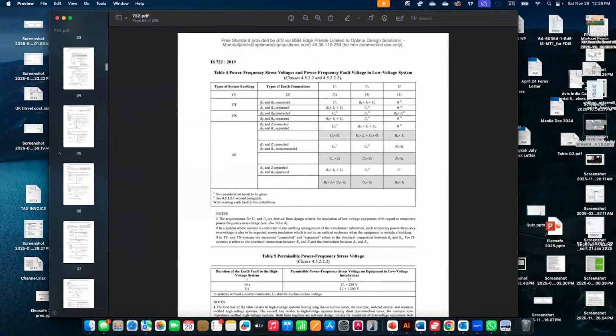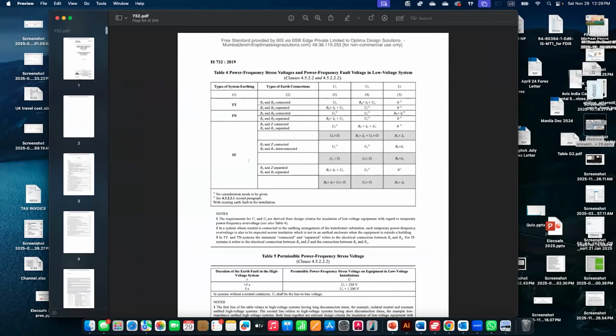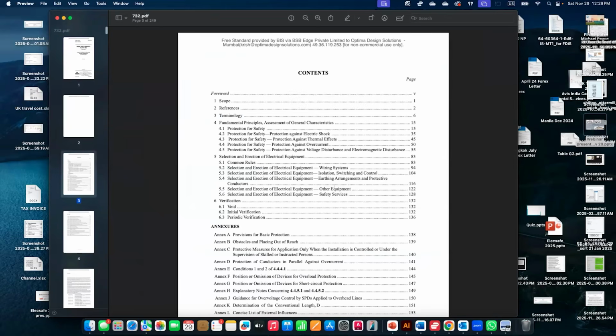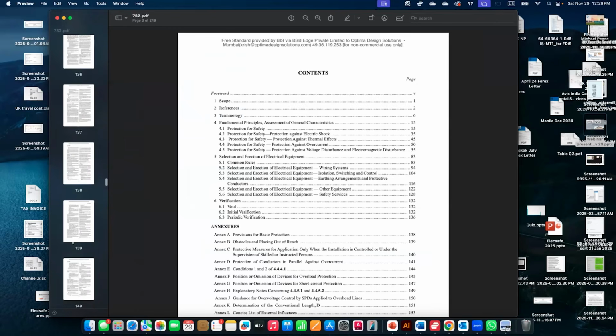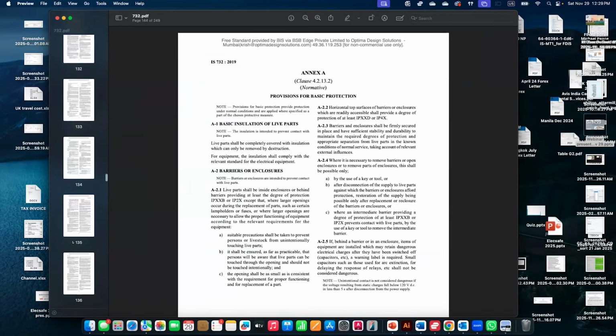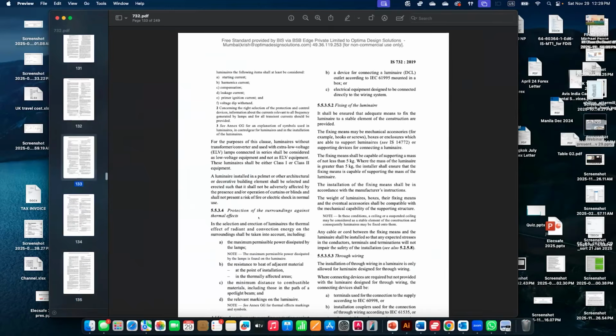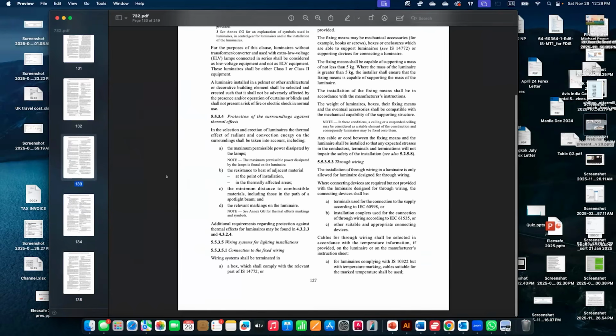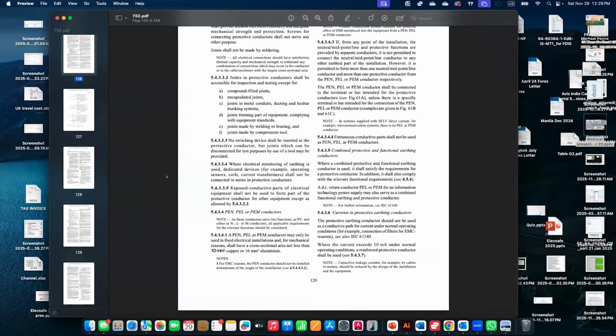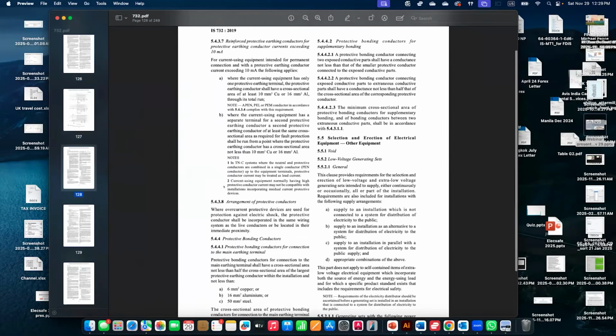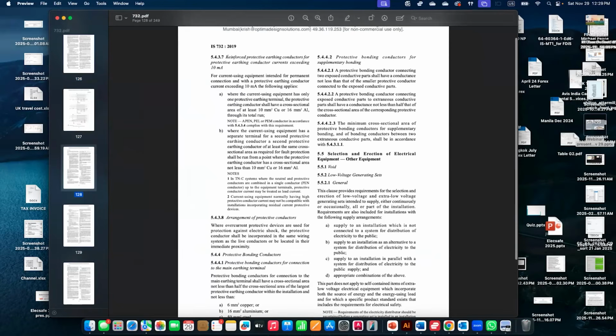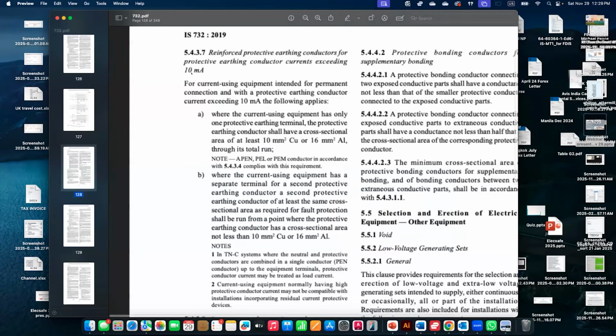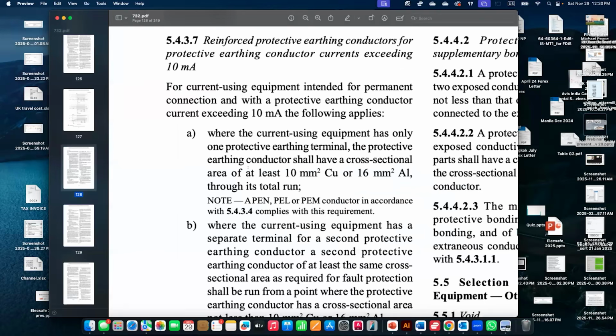Yeah. See, when you see IS 732, you need to go to part 5554, earthing arrangements and protective conductors, which is on page 116. So I'll go to page 116. Yeah, and there is the sizing. Now, if you have protective conductor currents higher than 10 milliamps, there are separate requirements.